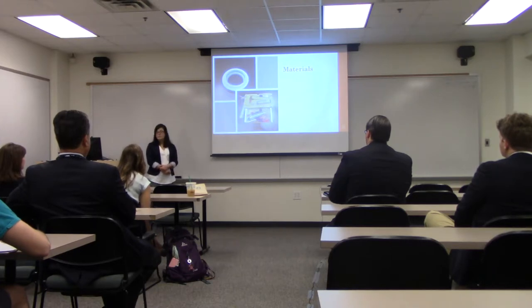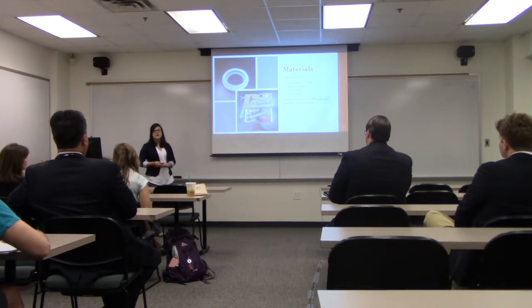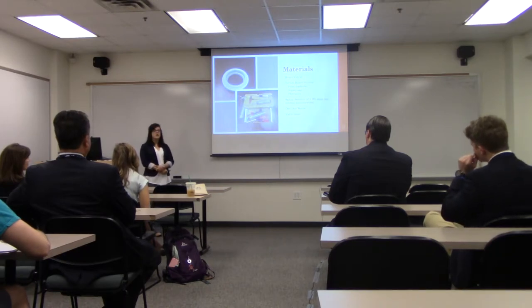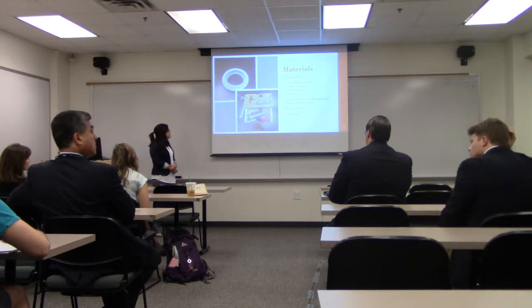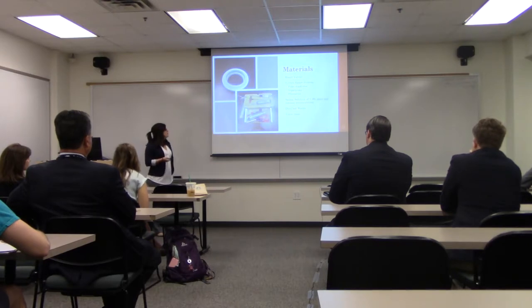An overview of the materials used: the heart valves discussed earlier, the heart system we just saw, saline solution at 0.9% mass per volume concentration to enable proper readings through the flow meter, as well as distilled water, valve seals to ensure no leaks, and various tools for assembling and disassembling the heart system to place valves in and out of the simulator.